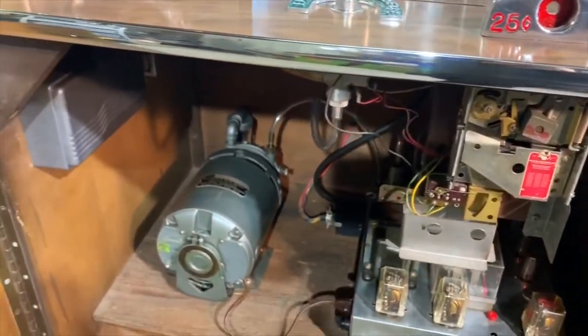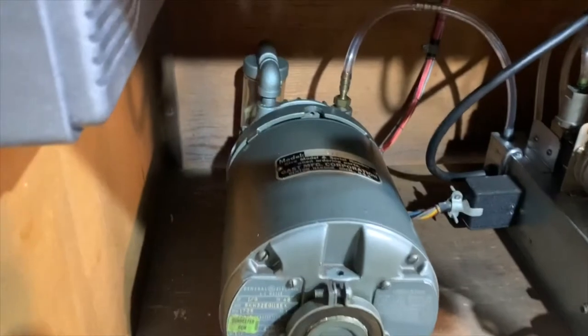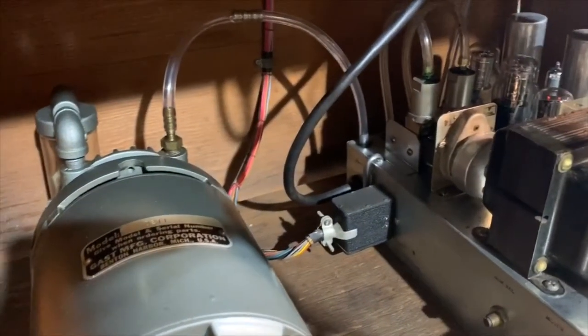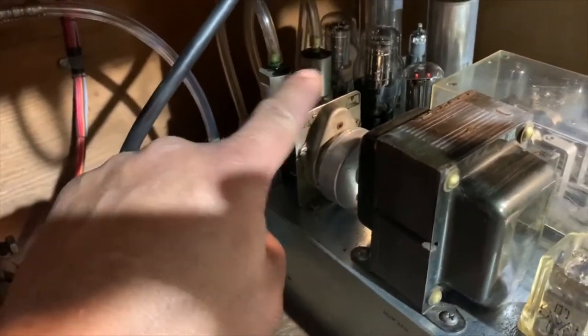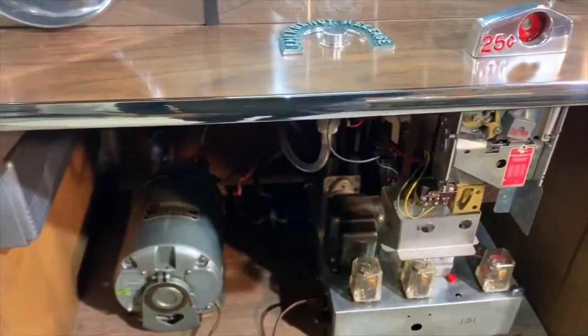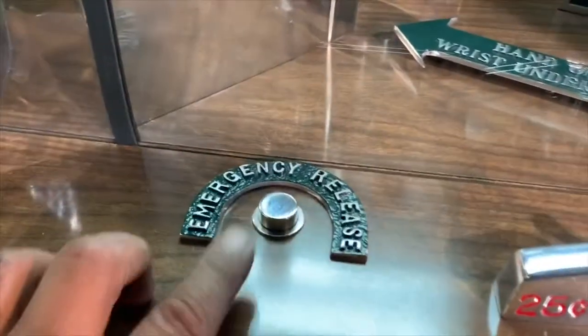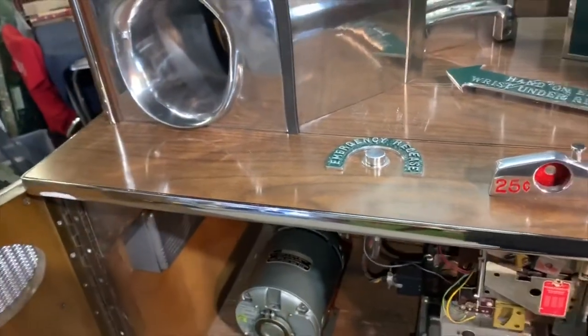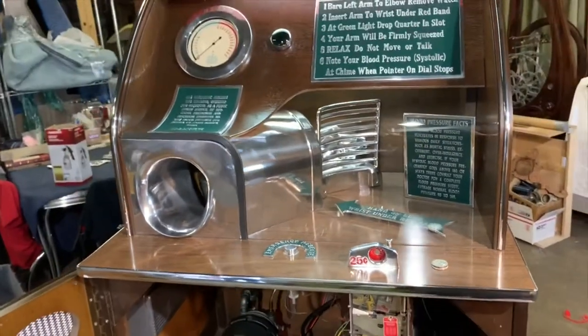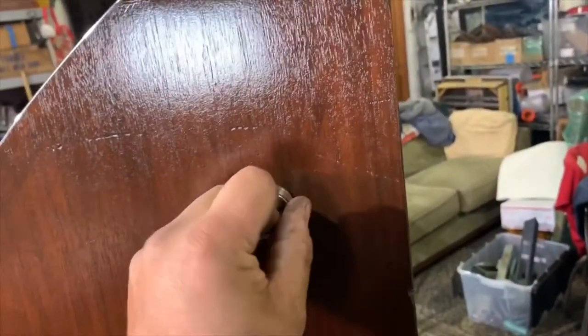You have a motor here and all this stuff is original. The motor has a filter in the back and pumps air into the amplifier. Over here these two little motors actually generate more air and that's what inflates your cuff. The first time I put my hand inside this thing I got a little nervous, and that can be the case for many people — so they added an emergency button. When you press it, it releases the air and shuts the machine down for a second before picking back up again. It's extremely bizarre and you've got to experience it.